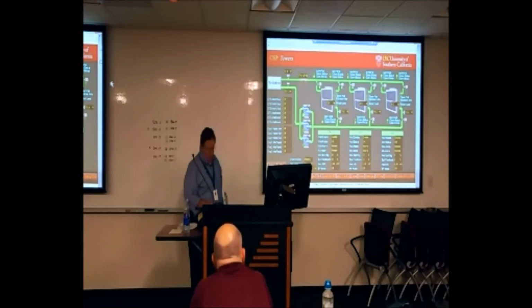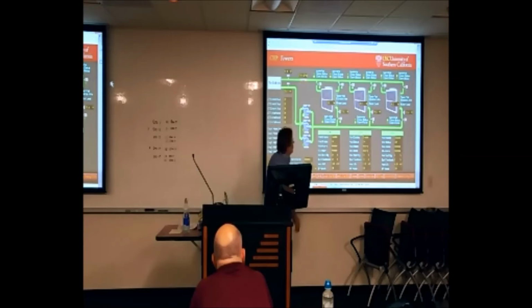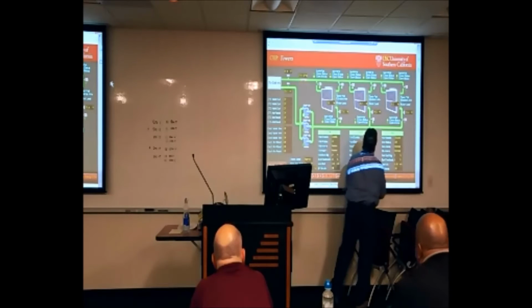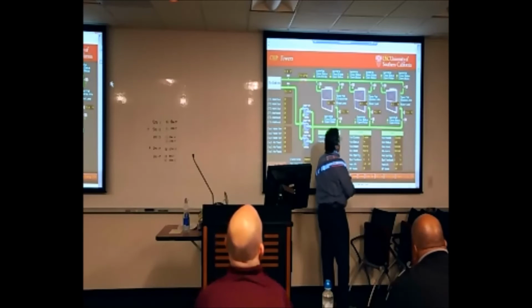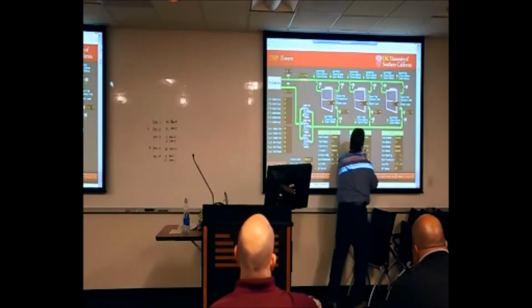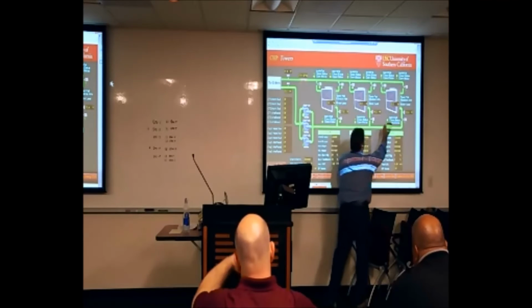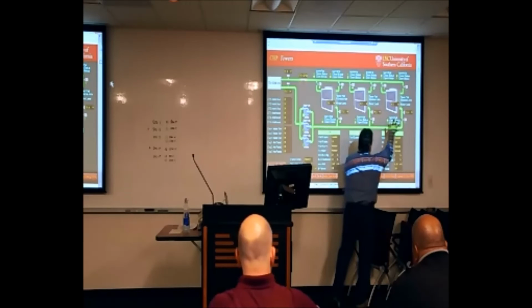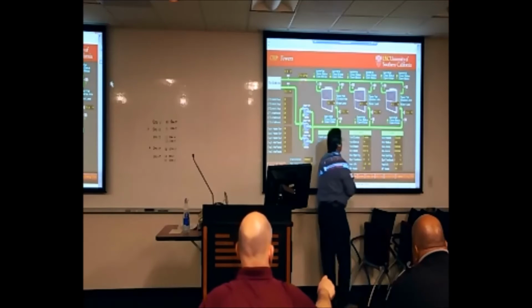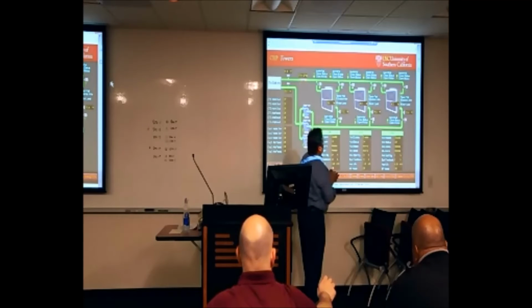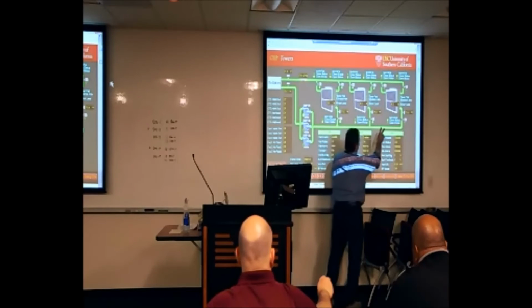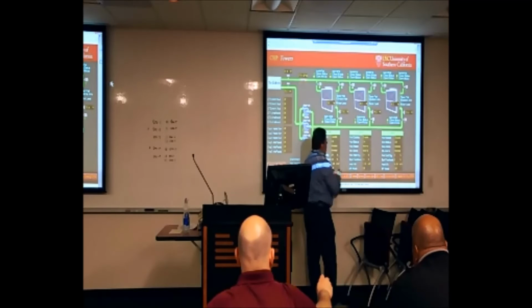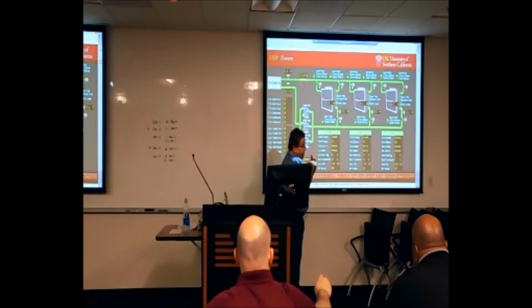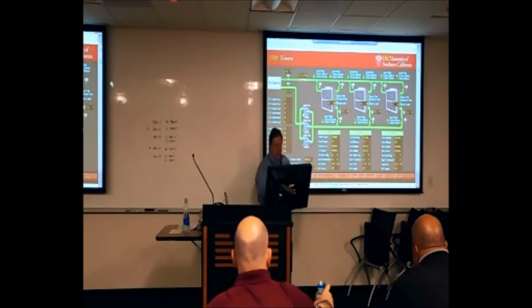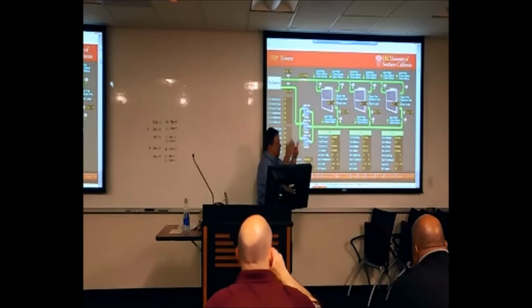Craig and I just went through the whole alarm sequence on the tower. We're having a problem with tower number 3, and on occasion, it's not being asked to run right now, but when it is, we've seen it several times now, indicate a tower fail alarm. But yet all the valves seem to be working, everything seems to be good, and so he and I were chasing this a couple of weeks ago, and as it turns out, we're getting a bad status signal from the drive, or it's loose wiring coming back to Honeywell, or it's a bad DI at the Honeywell system, but somehow we're picking up an alarm failure on that tower, and it's failing the tower.